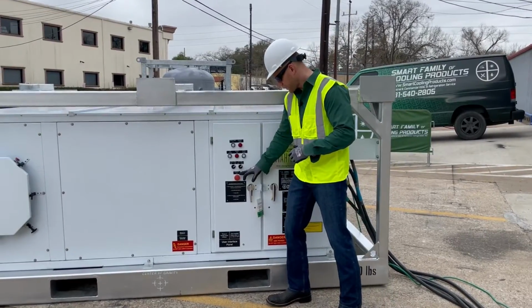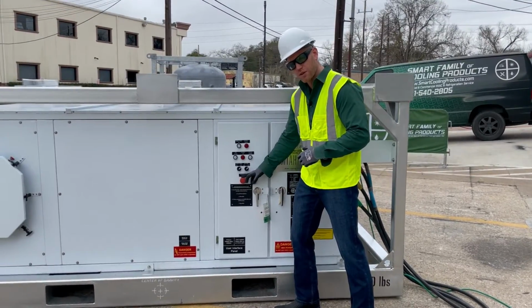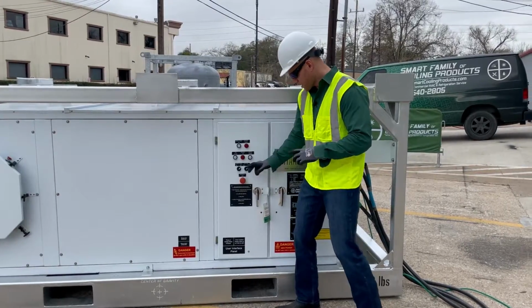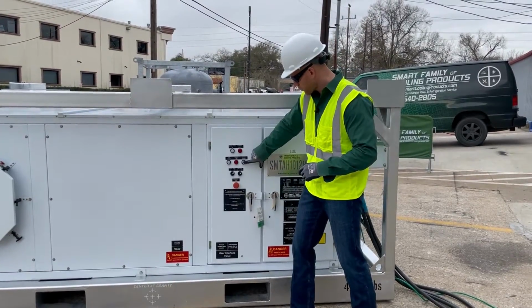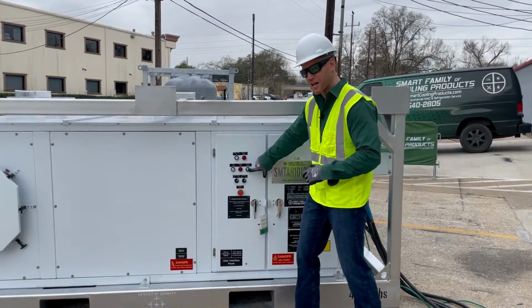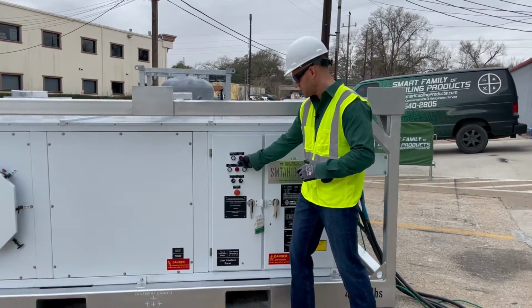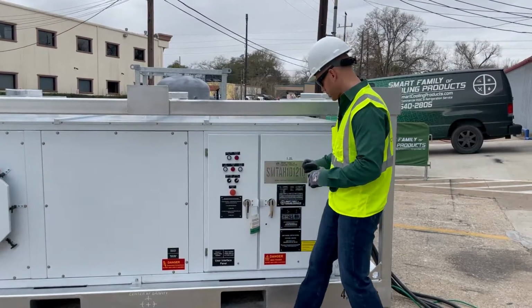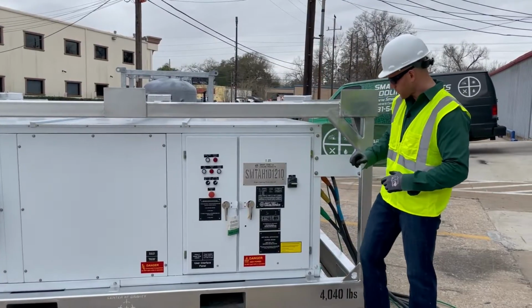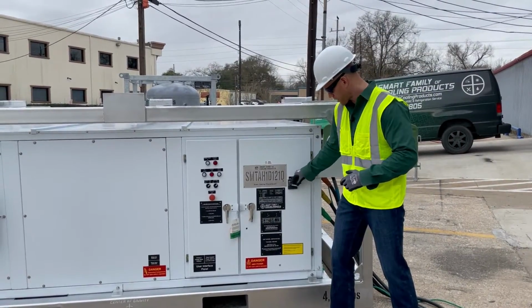Briefly here, I'm also checking my e-stop just to make sure that that isn't depressed. And when we get running, I'll show you here that all of our lights are push-to-test lights, so you can actually push these LED lights in to make sure that they're functioning properly.